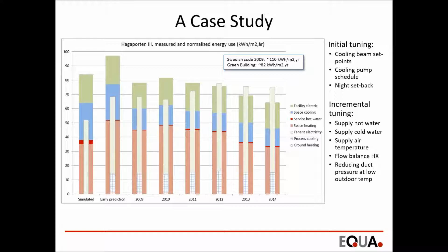So. Yeah, maybe you can change the next one. Yeah, and Mark, you will soon show some nice examples, and one of them is on night setback. What you can do in BAS. In this building, we introduced night setback in a very simple manner. We just changed the set point of the supply hot water temperature to the room heaters by 10 degrees between 5 in the afternoon and 5 in the morning.